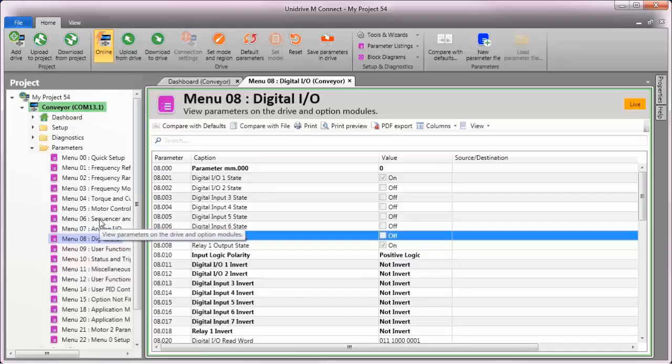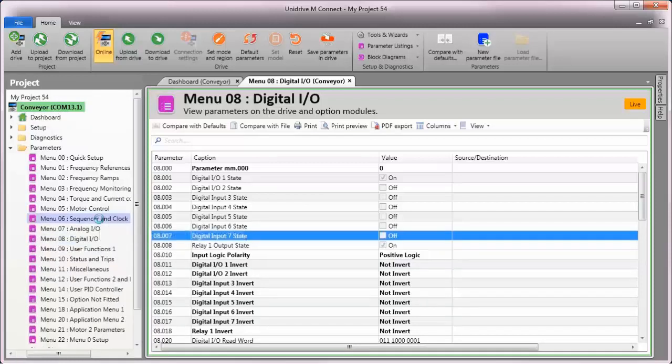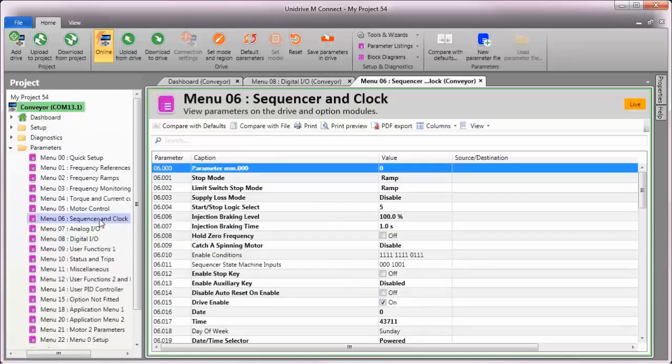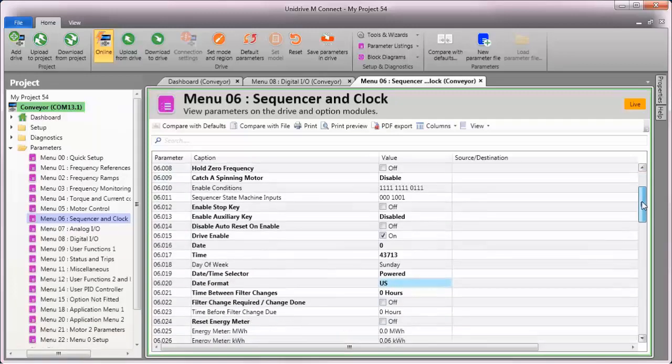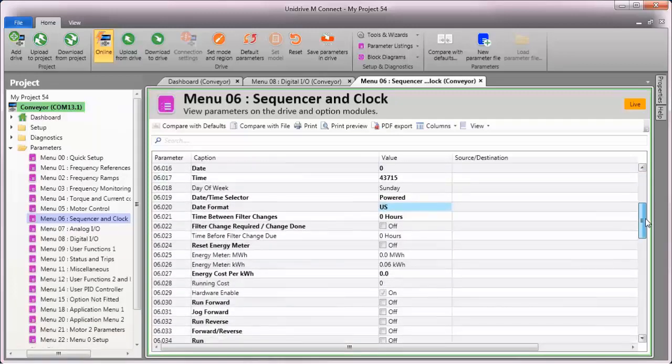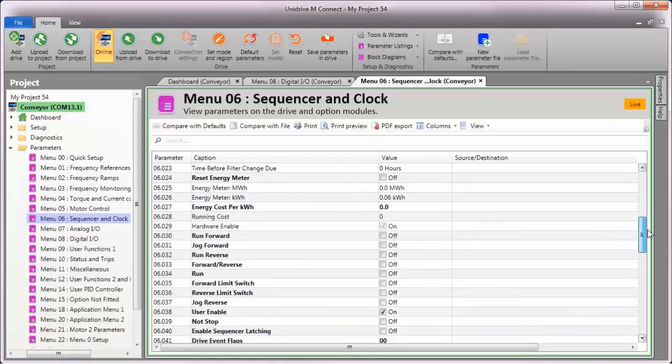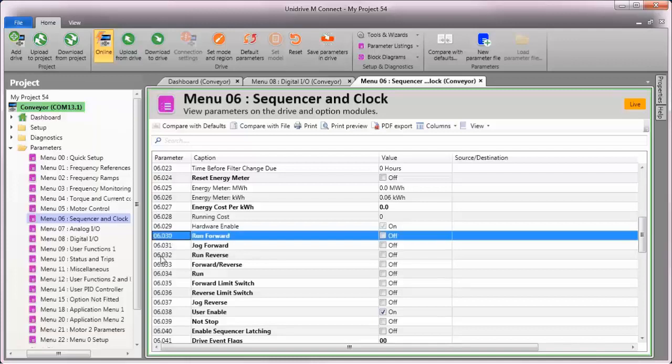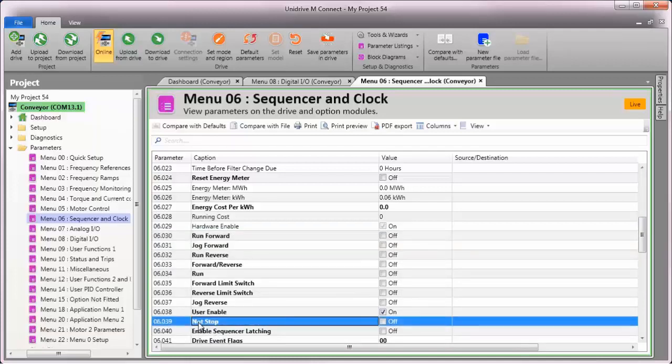Next, let's have a look at the sequencer in menu 6 to see what the parameter number is for the stop function. The sequencer functions begin with parameter number 30. You'll notice the parameter number 39 is labeled as not stop. This is the function I'd like to assign to digital input number 7.